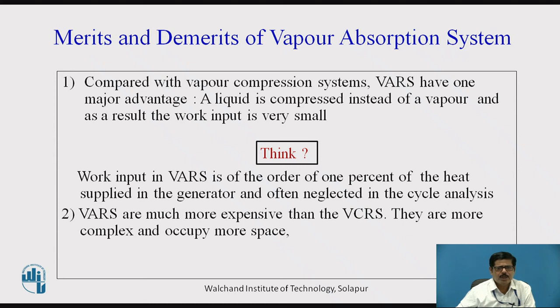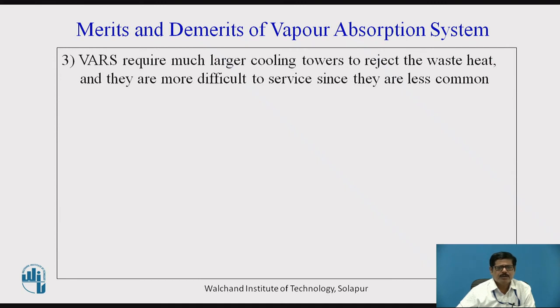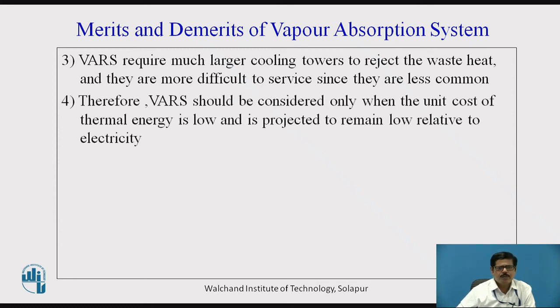VARS are more expensive than VCRS because absorption systems are complex, they occupy more space, and are bulky. So they are more expensive compared to vapor compression systems which are compact in nature. COP is much less, so they are less efficient also. Vapor absorption systems require much larger cooling towers to reject waste heat, and they are more difficult to service since they are less common. A large amount of heat is to be rejected in the condenser and absorber, so you require larger cooling towers. Vapor absorption systems are therefore considered only when the unit cost of thermal energy is low — meaning waste heat is available in large quantity, or heat is available at low cost compared to electricity.